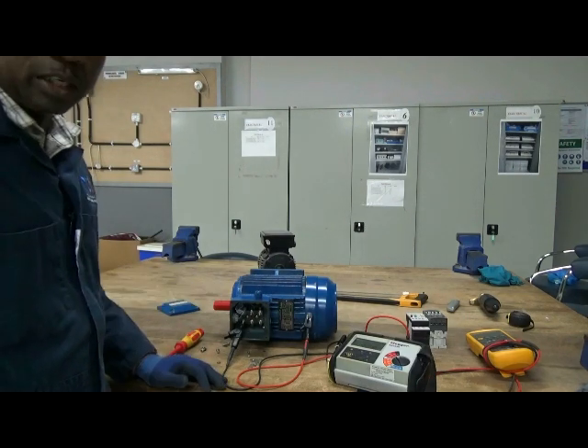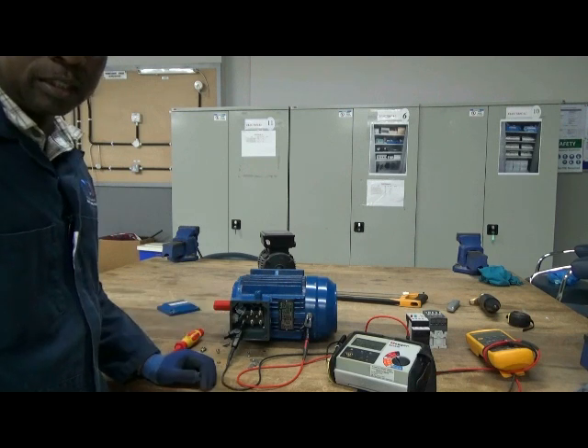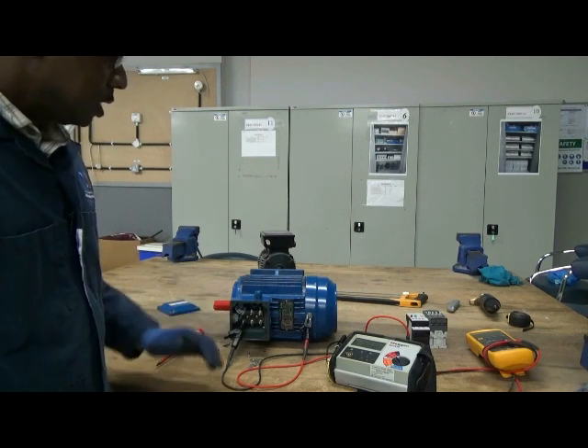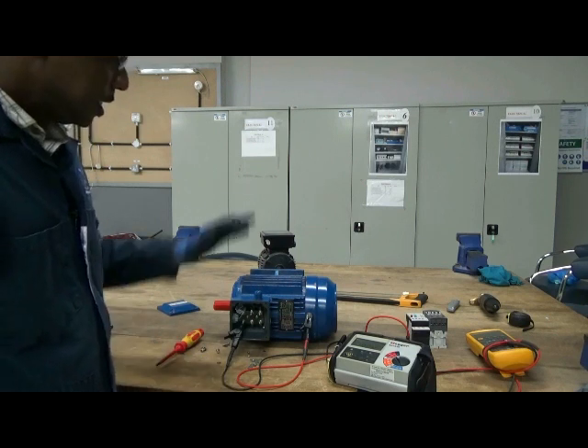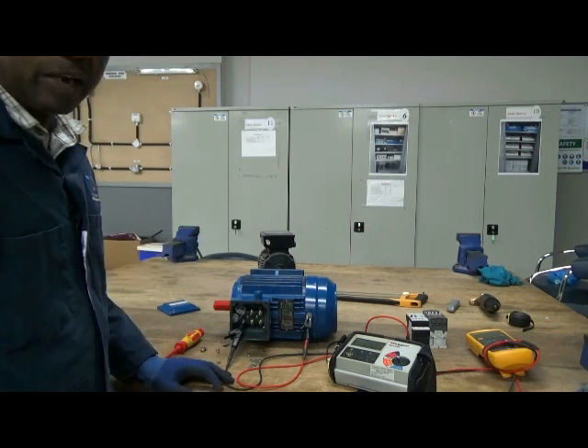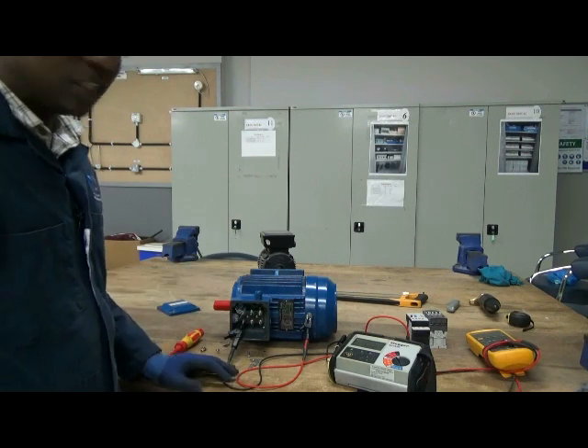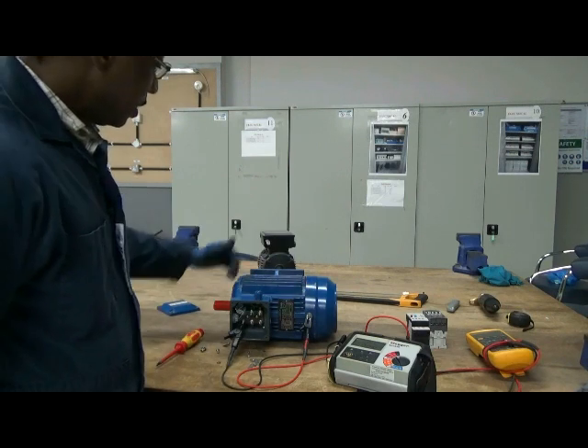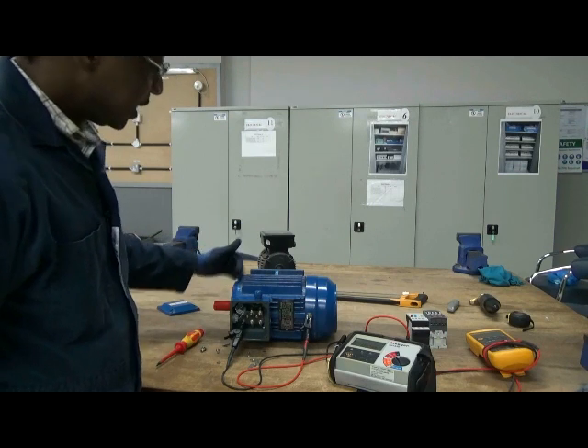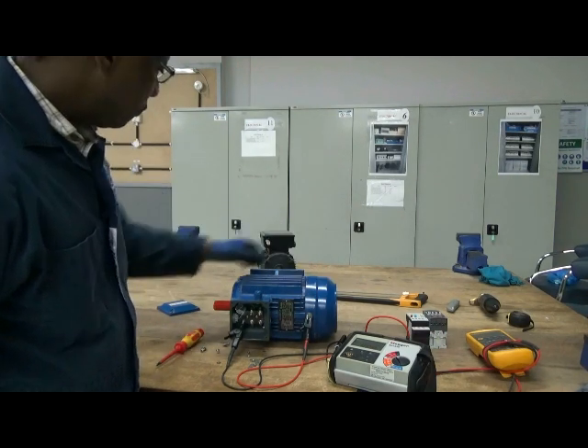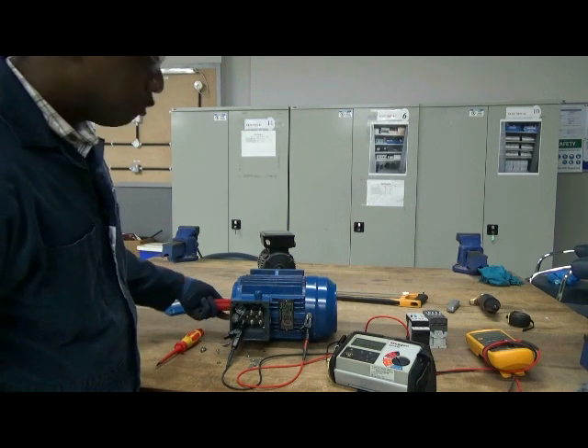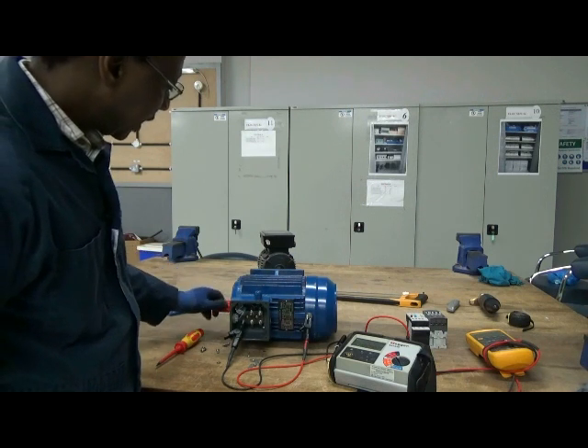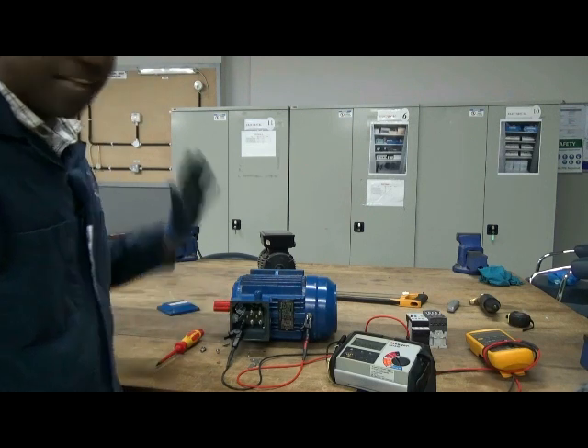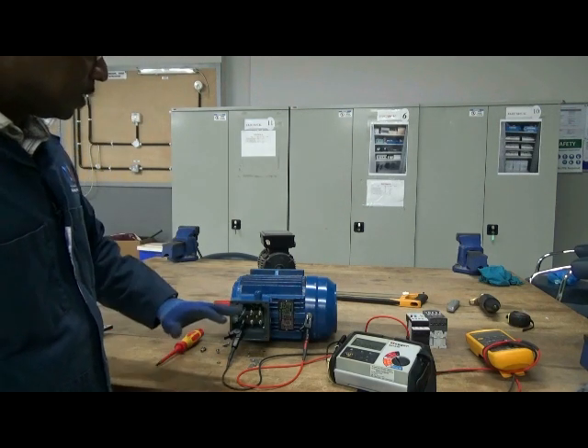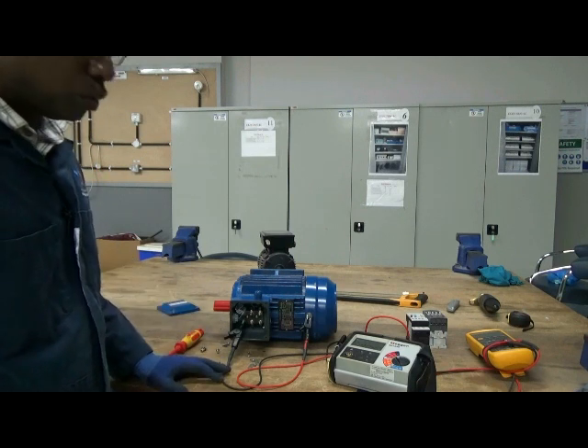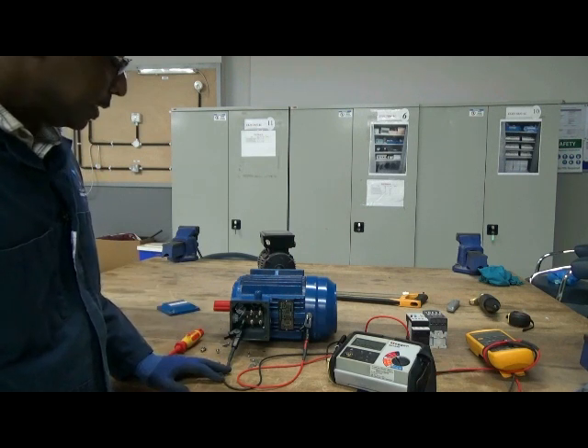It has got good insulation resistance between windings, and good insulation resistance between windings and earth. All windings are balanced. That means this machine can be connected to the supply with no doubt, as long as the bearings are sound. Remember, there are two bearings, one on each end. If the rotor can rotate freely, just by pushing it, I can see that the bearings are sound. Then I can connect it to the supply because the machine has passed all the recommended tests.